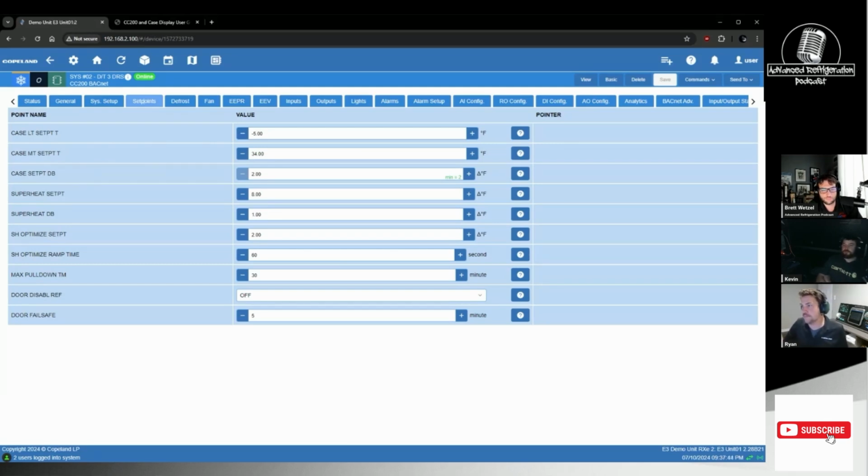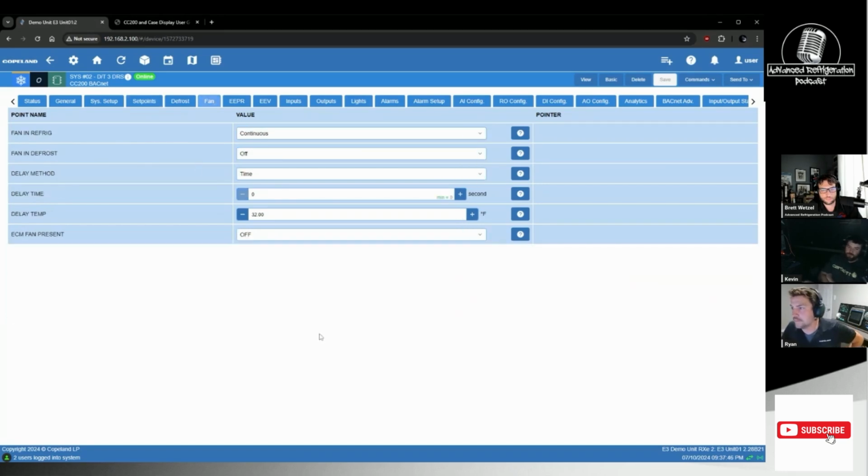You could literally control the TD of coils and get the most efficient coil you could. On a big coil, it would pan out. On a case with 6,000 BTUs, it seems like a giant waste of money, but on a massive coil with a 30-ton valve, huge savings. You can really fine tune it. Yeah, on medium and high profile evaporators, you can definitely fine tune it.